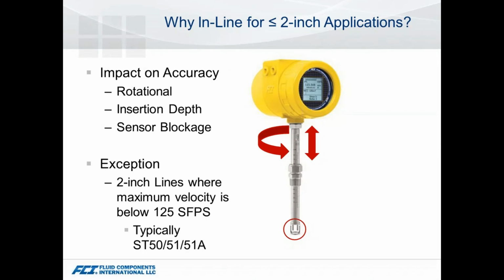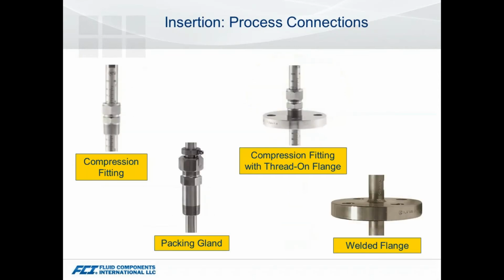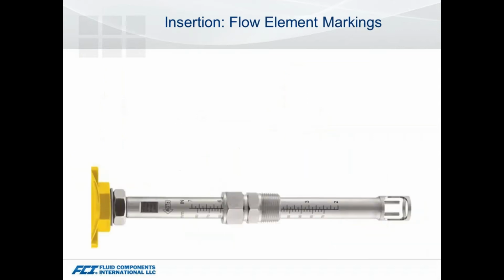There are some exceptions that we've had with the 2-inch lines, primarily going to an insertion style with the more economical units. But there's a limitation there as far as the flow range capability compared to the application capability in 2-inch and larger lines. Process connections, a range of options, from compression fittings and packing glands that allow you some adjustability in the field. Packing gland giving you the added option if you're going to be removing an instrument on a regular basis for any type of preventative maintenance. It's the most flexible there. Flange types, you have to look at if you go to a fixed flange, now you're paying more attention to your installation details. So compression fittings and packing glands give you a little bit of leeway that you don't have with a fixed installation.